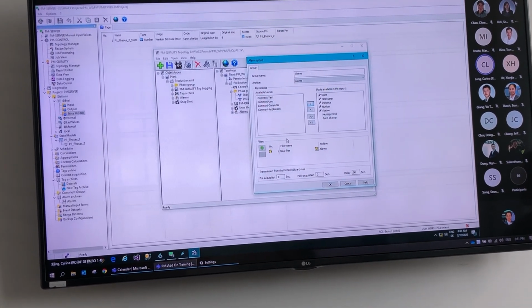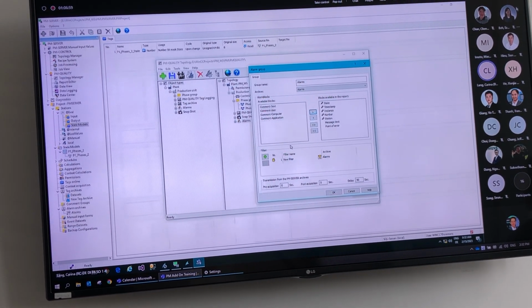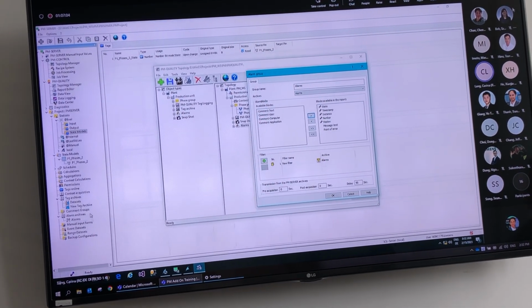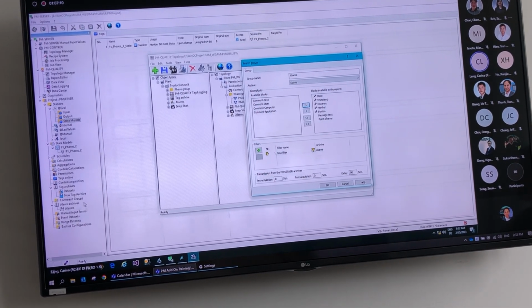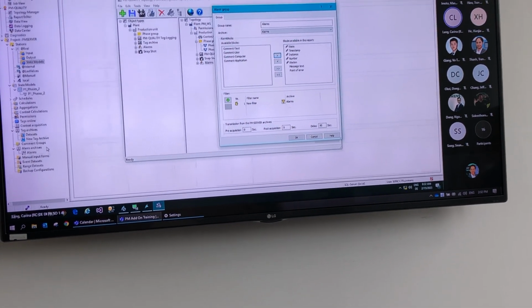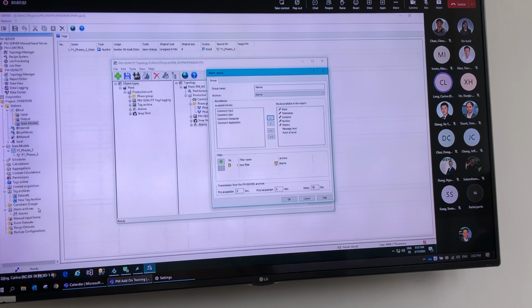We can also have some filters inside of this alarm group of PM quality. So we remember in the alarm archive, if you go back to the PM server in the background here, we have some filter settings, and if we have some filters inside of the alarm archives in the PM server, that means we do not store the alarms which do not fit the filter. Right, so we just store all the alarms which fit the filter, and all the other ones are not copied from WinCC to the PM server, as they do not fit the filter.